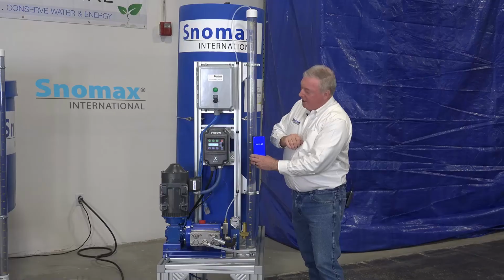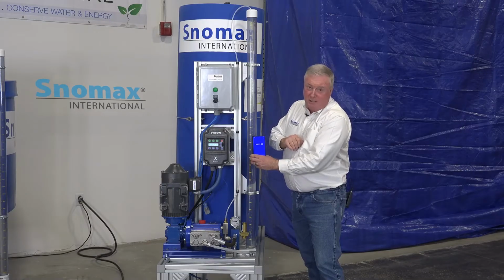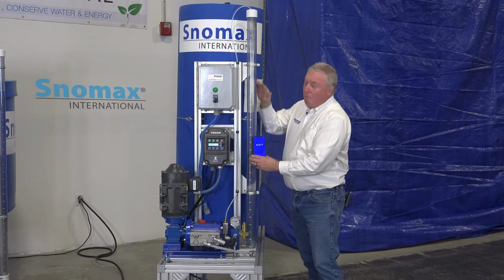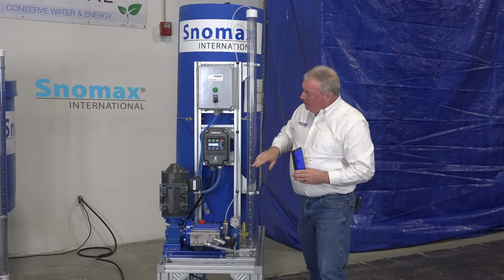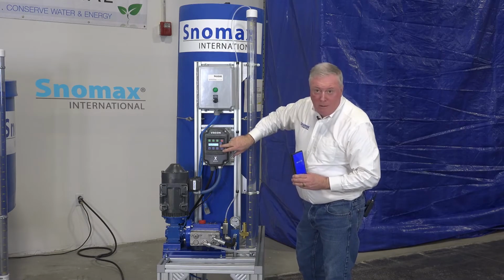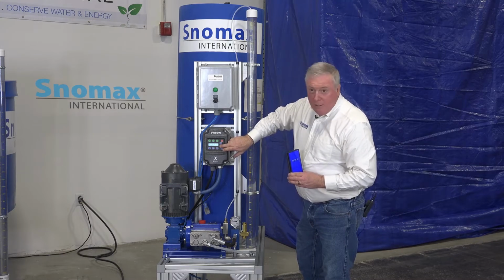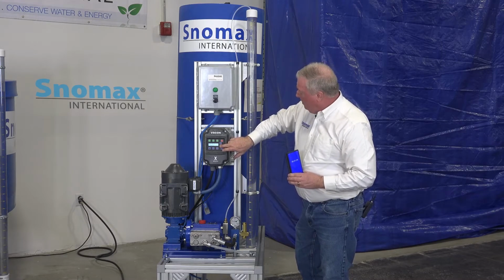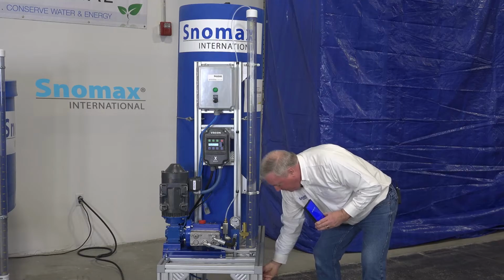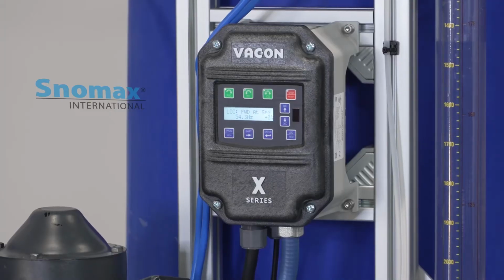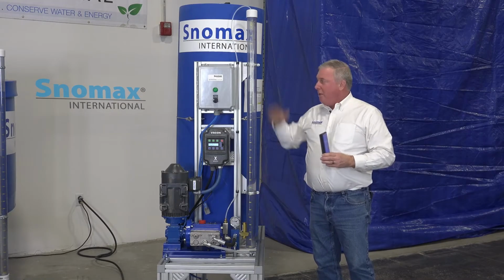We got to basically where we're supposed to be in 30 seconds, and we should have taken a whole minute to get there. So I'm running twice as hot. So I'm going to go over here and adjust the speed of the pump downward, and then we're going to open the valve, let it flood back up again, and then do another calibration, and we're going to keep doing this.